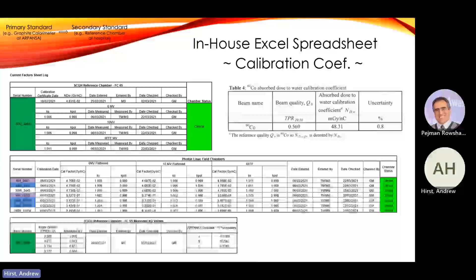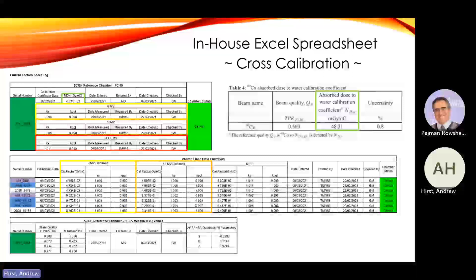Yes, kind of. I'm pretty sure our linacs are very much beam matched, so we can use the same KQs for all our linacs. When I pull up my spreadsheet for a measurement, I'm fairly certain the linac itself doesn't change the KQ. It's still the same one for the chamber, just because of how beam matched our linacs are. But the one at the standards lab isn't the same. I was going to say, if the patient had to receive multiple treatments and went to separate linacs, you'd have to correct between those. But yeah, they're being matched. And we define the output every month for every linac anyway.